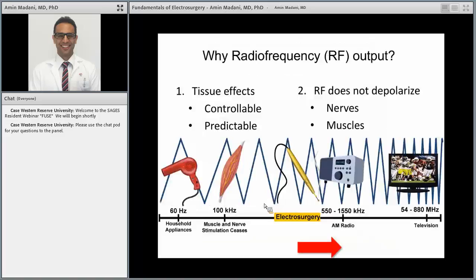So just to demonstrate again, the wall output is 60 hertz, and electrosurgery is about 500,000 hertz. So you've bypassed the ability of muscles and nerves to be stimulated. So in that case, you don't electrocute the patient. Instead, you're enabled to deliver very controllable and predictable tissue effects when you activate the device.